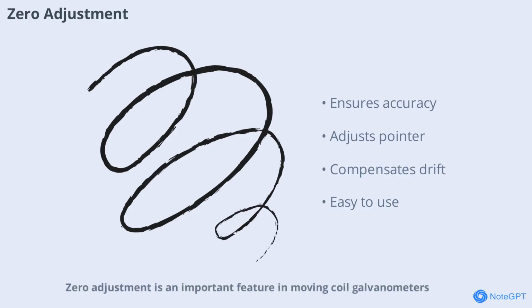Zero adjustment is an important feature in moving coil galvanometers. It allows the user to set the pointer to zero before taking measurements, ensuring accuracy. This is usually achieved by adjusting a screw or knob that changes the tension in the suspension system. Regular zero adjustment is necessary to compensate for mechanical drift and maintain reliable readings over time.